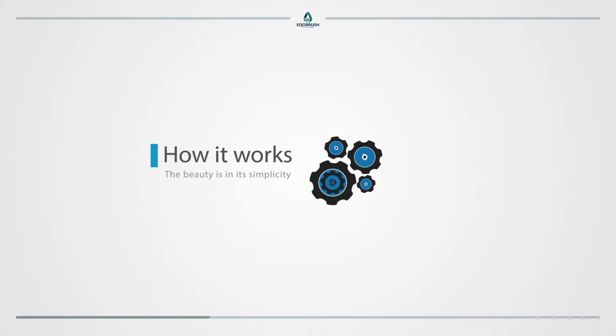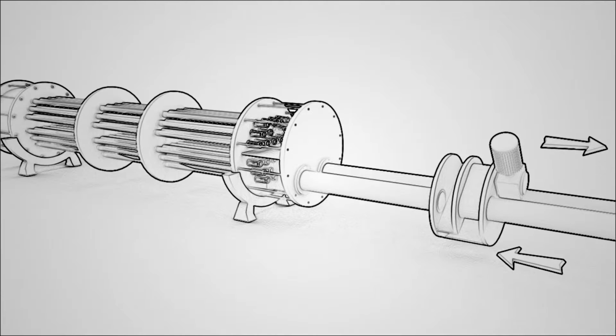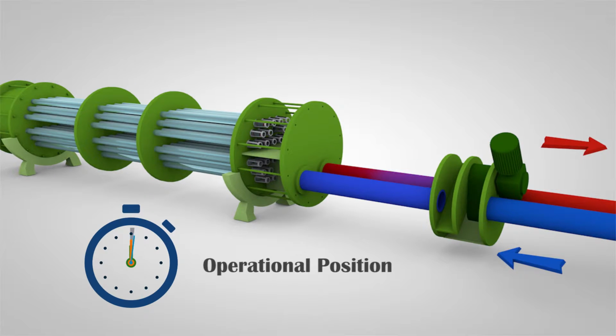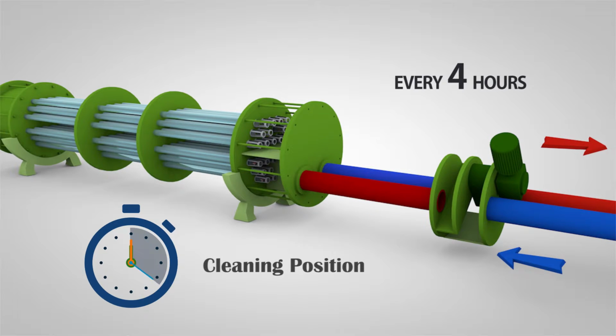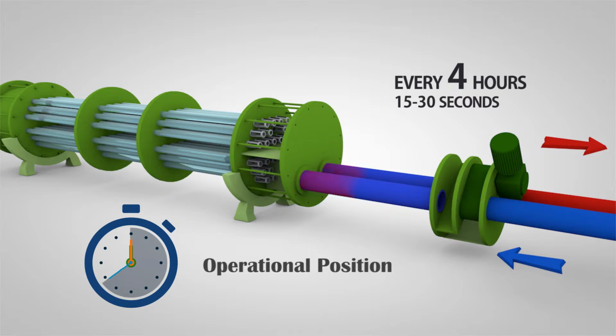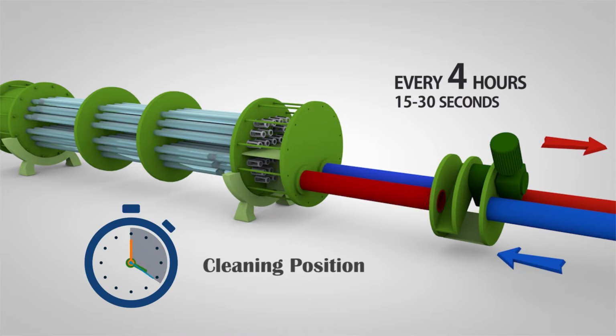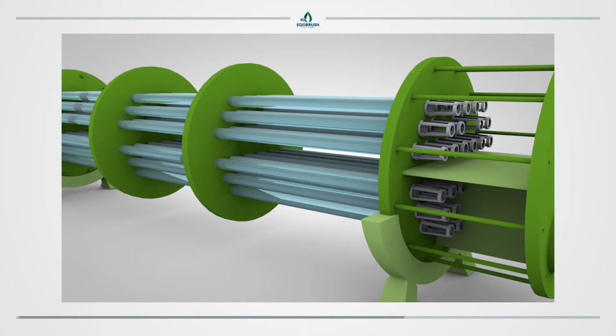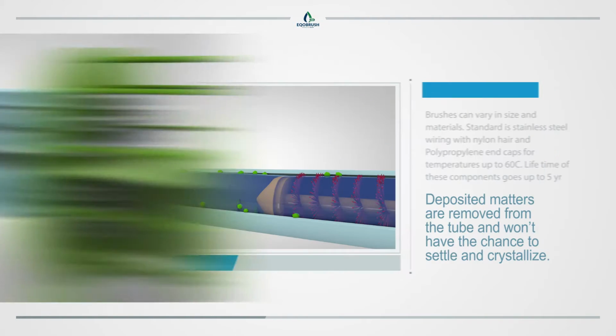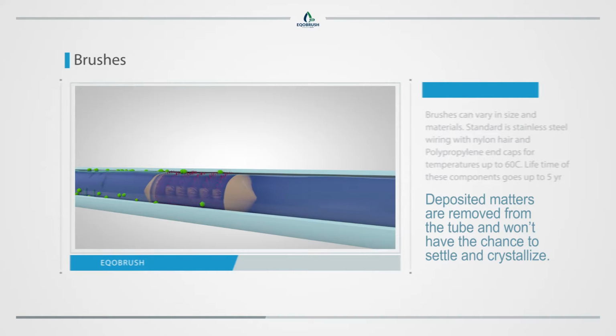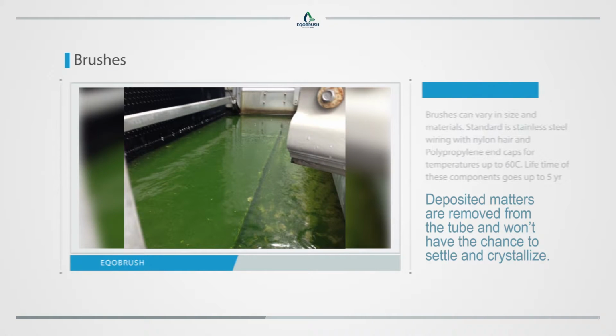How it works. The beauty is in its simplicity. The automatic valve reverses the water flow in the heat exchanger every 4 hours for about 15 to 30 seconds without affecting the flow to the cooling tower. The heat exchange process will not be impacted in this short interval. The nylon brushes travel up and down the tubes, pushed by the water. Deposited matters are removed from the tube and won't have the chance to settle and crystallize. All removed matter eventually settles in the cooling tower basin.